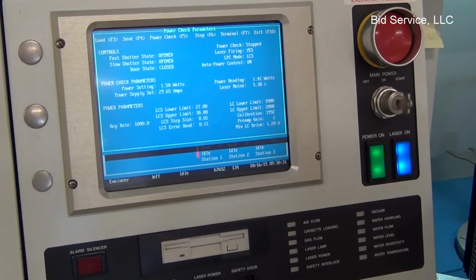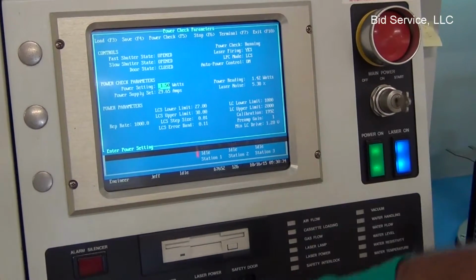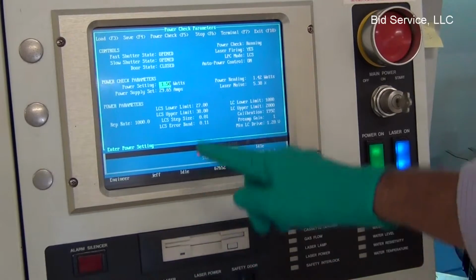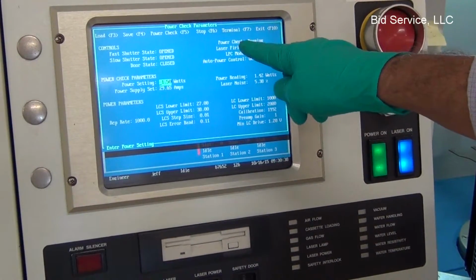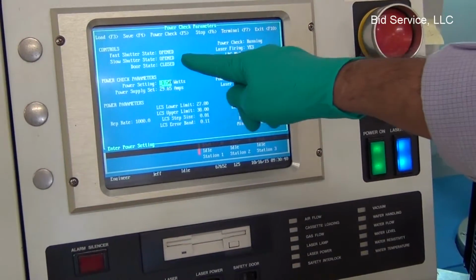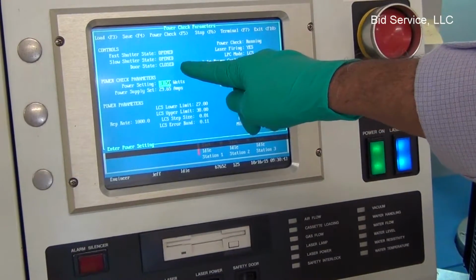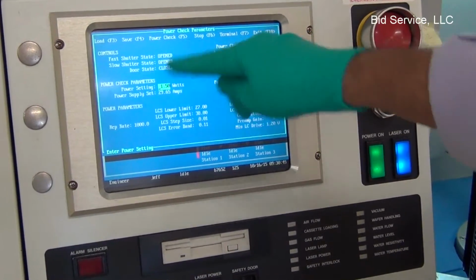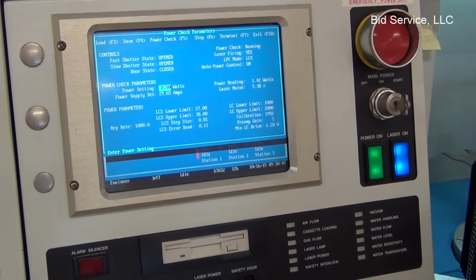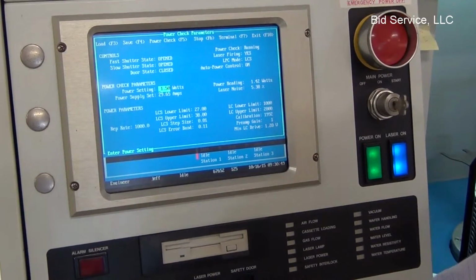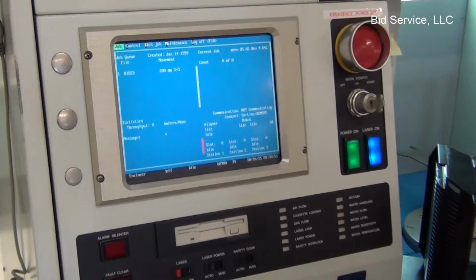The lamp current should not exceed 38 amperes, and the repetition rate can be adjusted depending on the requirement. So to do the power check, I am using function key F5, and at this moment the power check is running, and accordingly the shutter doors will change. So to escape from this screen, press the escape button.